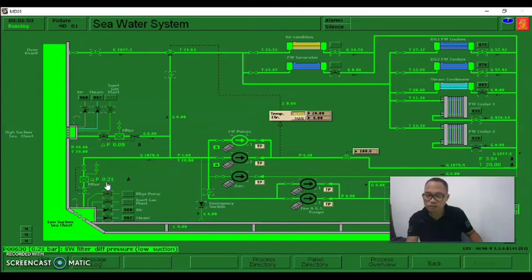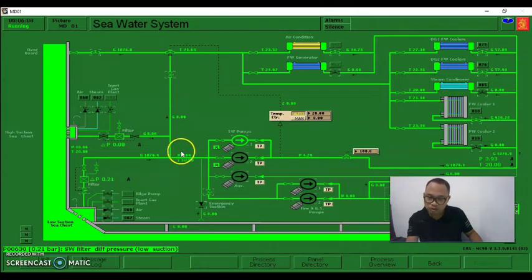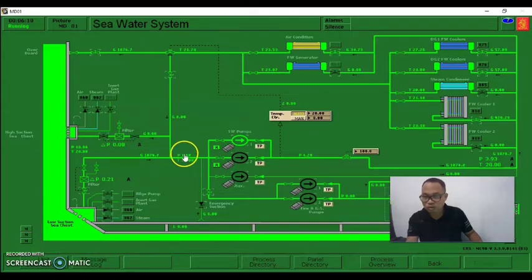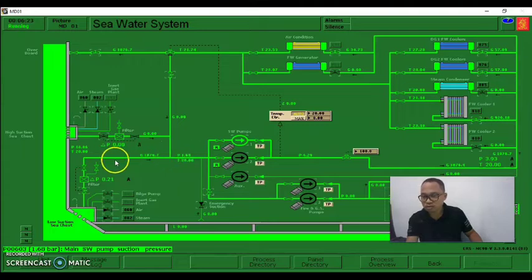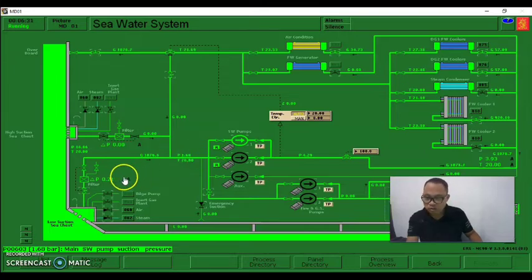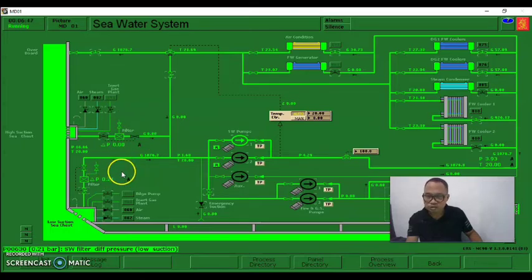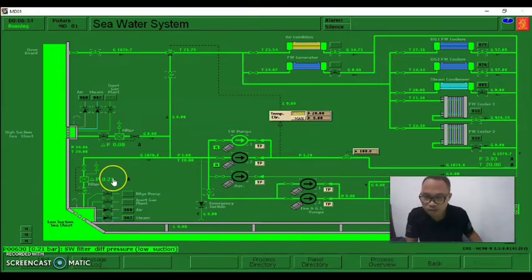The differential pressure must not reach 0.8 bar - it must be less than 0.8. It's just 0.21, which is okay. Monitor the pressure of the seawater - the pressure is 1.68, which is good. It must be 1.6 and above. This is our seawater pump suction pressure going to the pumps. The differential pressure is about 0.21 bar, which is good - less than 0.8, so our low suction switches are clean.